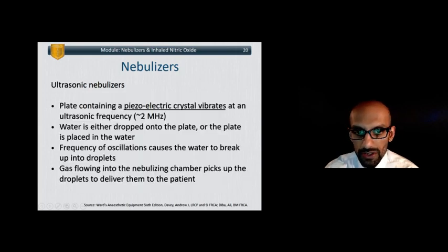Ultrasonic nebulizers use the process of sonication to nebulize water and other solvents. There's a plate containing a piezoelectric crystal. Piezoelectric crystals are basically membranes that deform, and when they deform, that's a form of energy that gets converted into an electric current. That's essentially what that is. And these crystals vibrate at an ultrasonic frequency, around 2 megahertz, very fast.